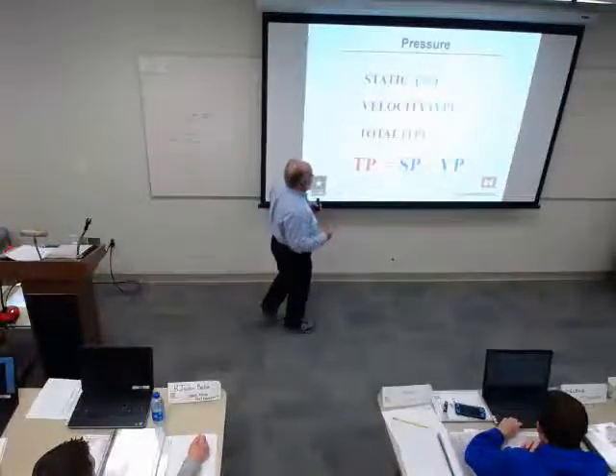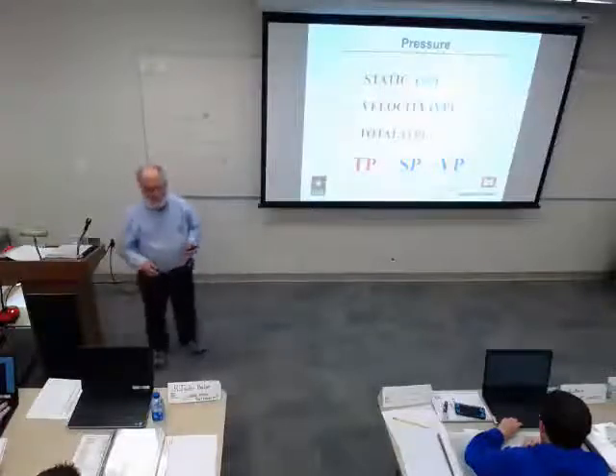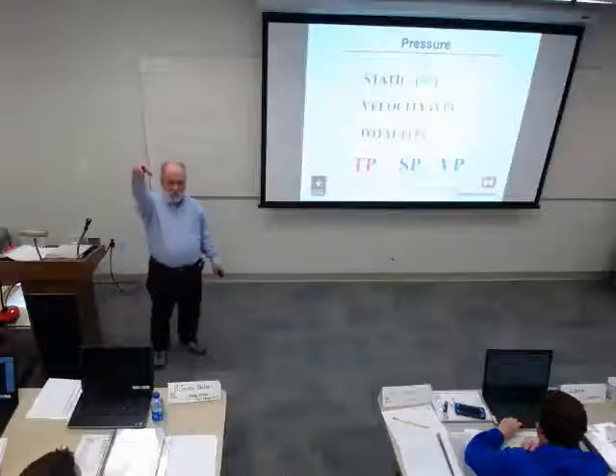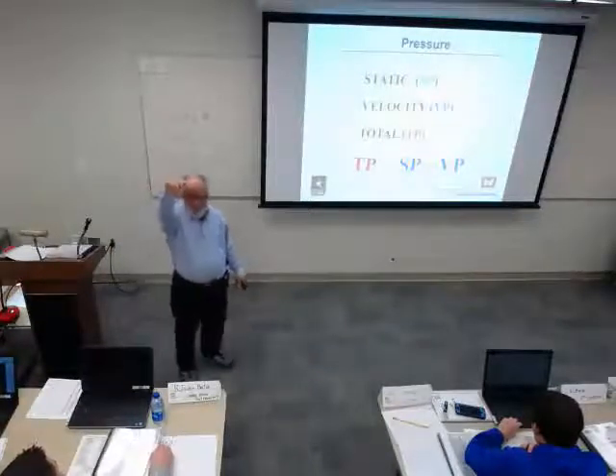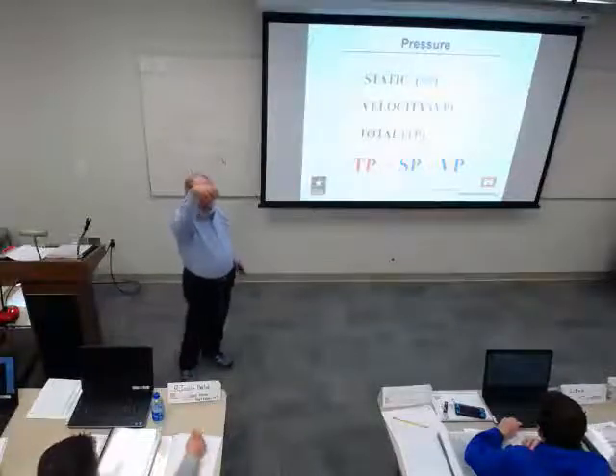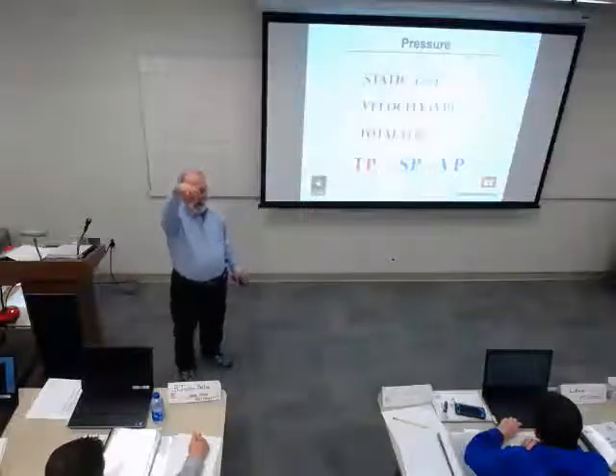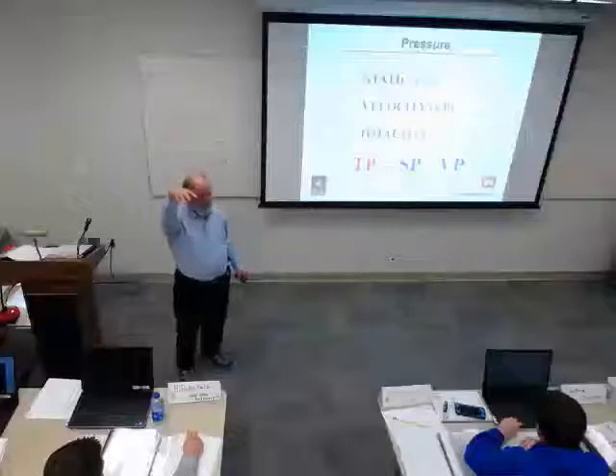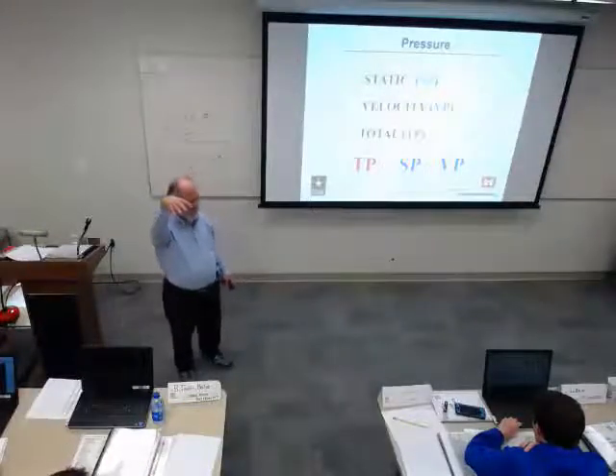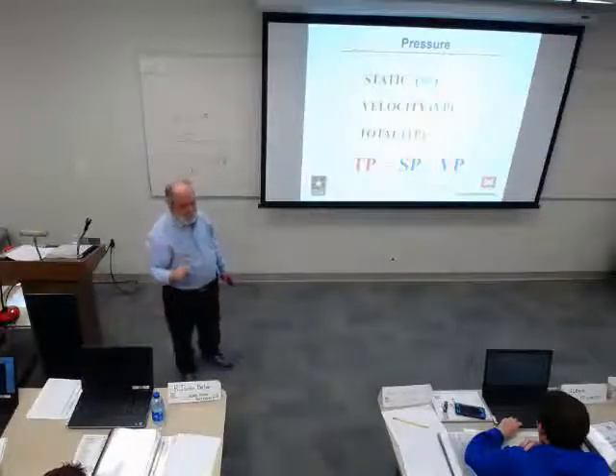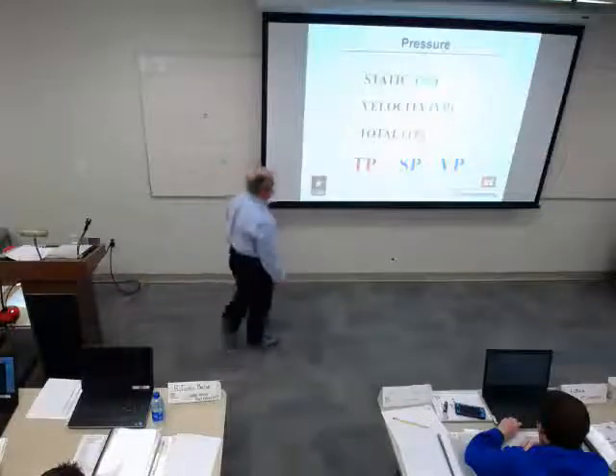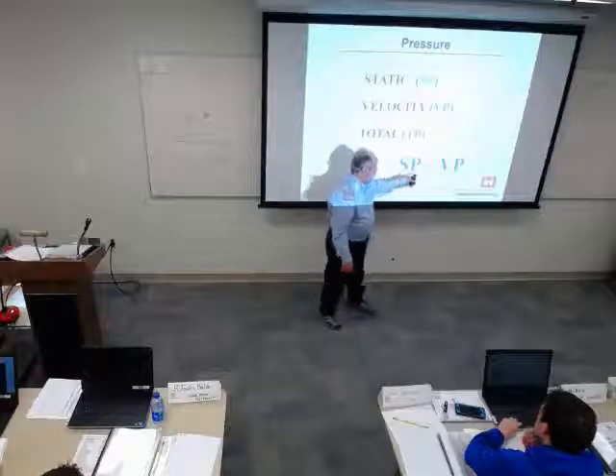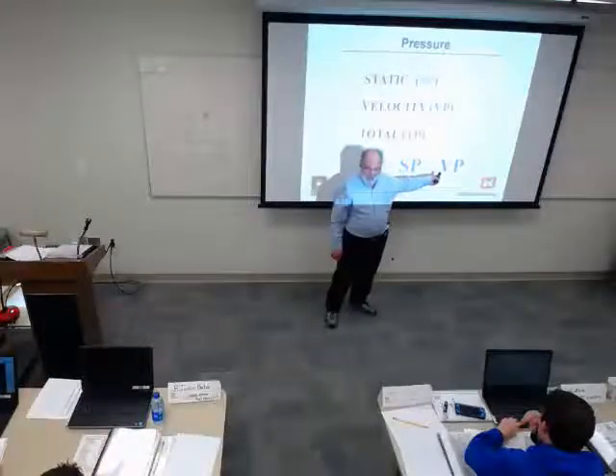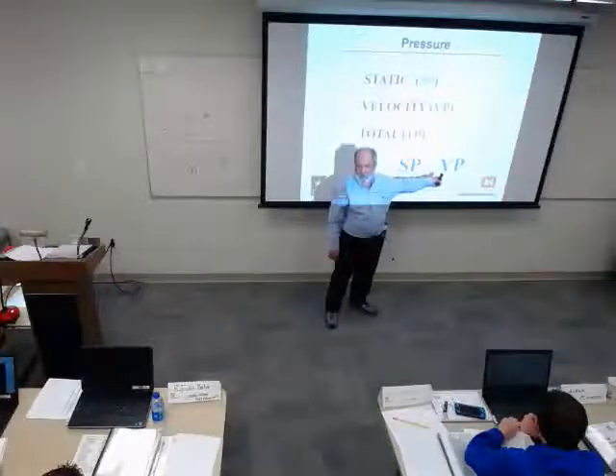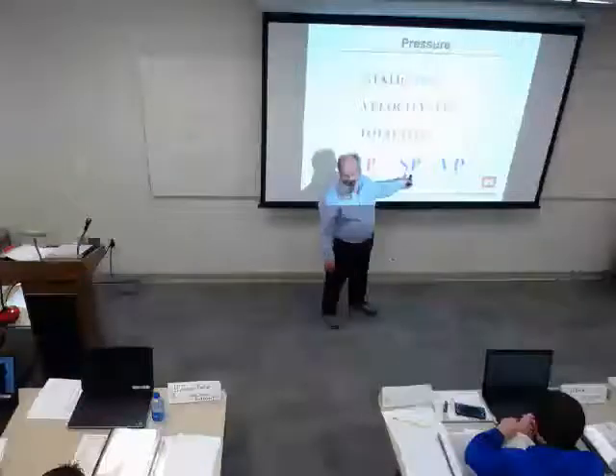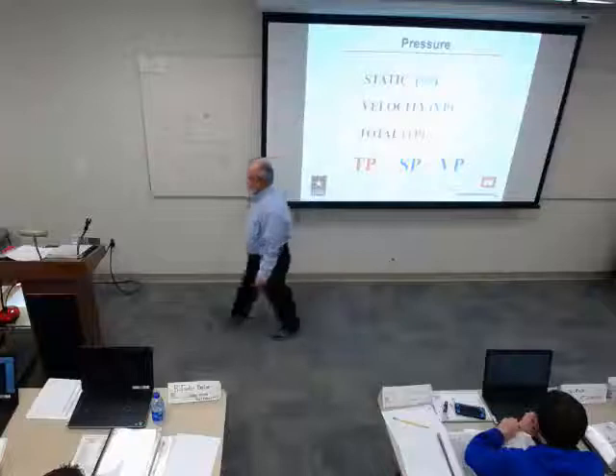Something that's useful to remember is that static pressure is kind of analogous to this: let's say I have a ball, I'm going to drop it, and the energy represented by the ball at this height is the potential energy. So static energy is potential energy. When I drop the ball it begins to move, gains speed, and gets energy associated with its movement: kinetic energy, velocity energy. So static energy gets converted to kinetic energy, and that's really what goes on here. As you go down the duct, the velocity energy is being dissipated by friction and all the things that it impacts. Its storehouse is static pressure. If you keep that in mind, it helps keep some things untangled.